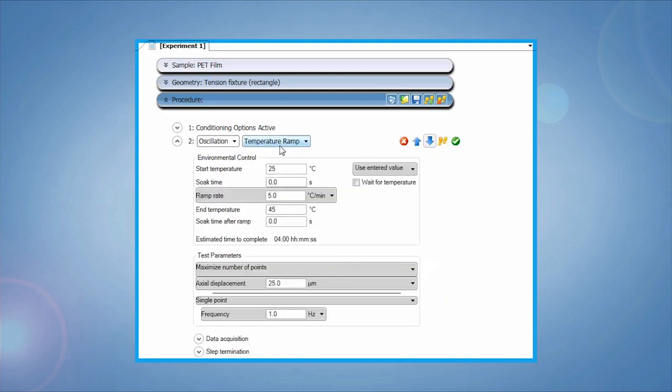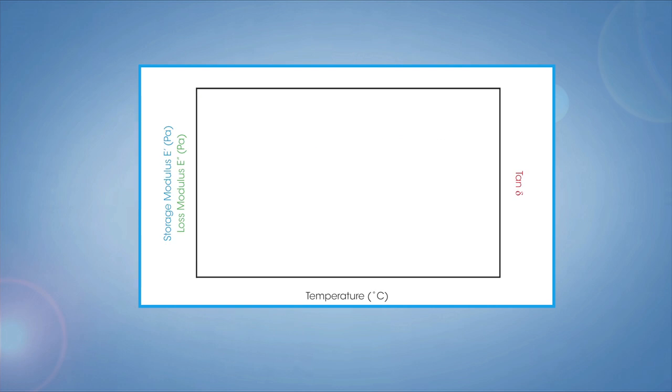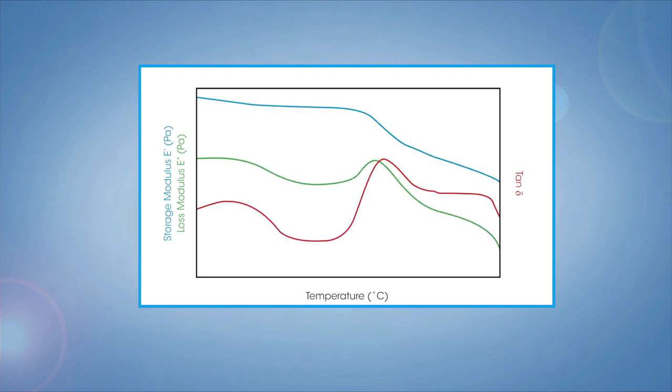This oscillation step can include an amplitude sweep to determine the linear viscoelastic region, a frequency sweep for viscoelastic characterization, a time sweep to determine stability, or a temperature ramp or sweep to measure thermal transitions and modulus as a function of temperature.